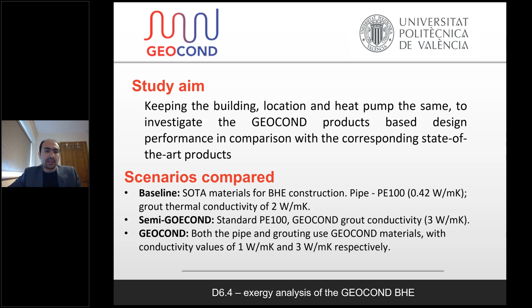Improvements in the GeoCOND project for the pipe increased conductivity from 0.42 to 1 watt per meter Kelvin, and for the grout, it increased from 2 watts per meter Kelvin to 3 watts per meter Kelvin. So essentially, with these improved values, how does our BHE and the ground source heat pump system perform is what we're trying to find in this study.